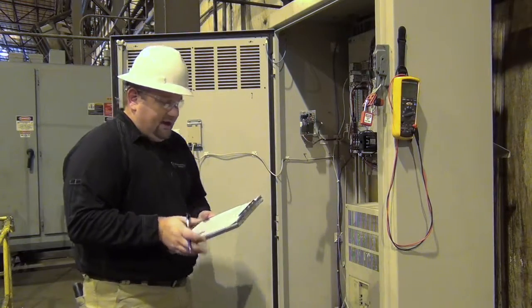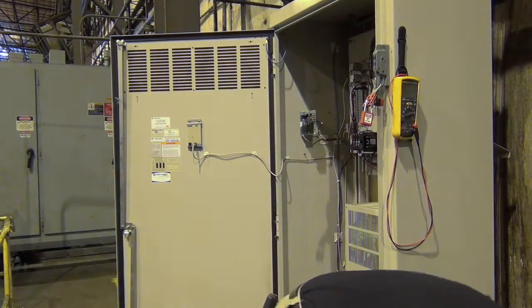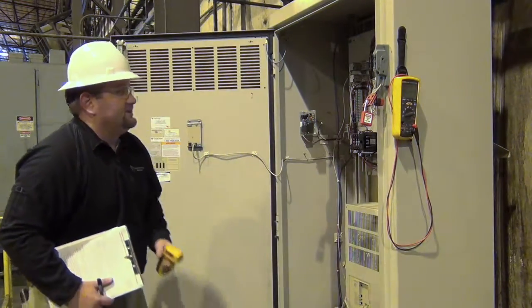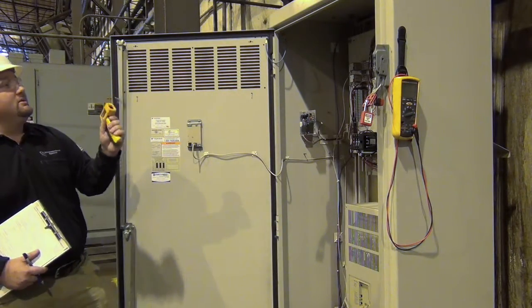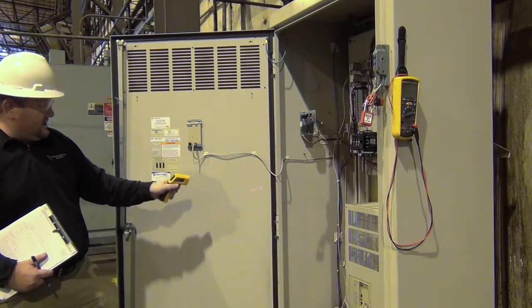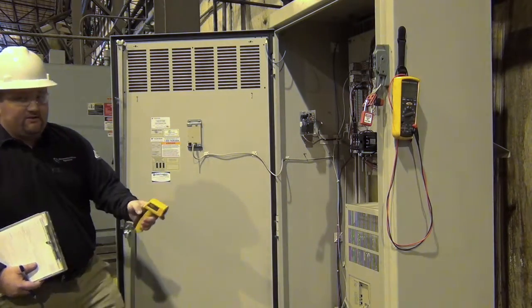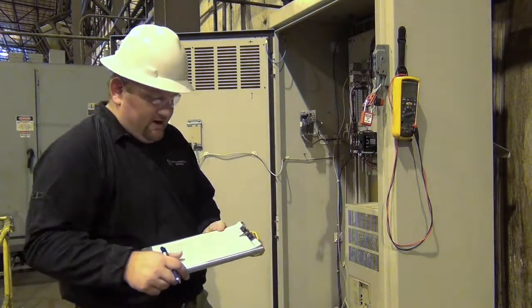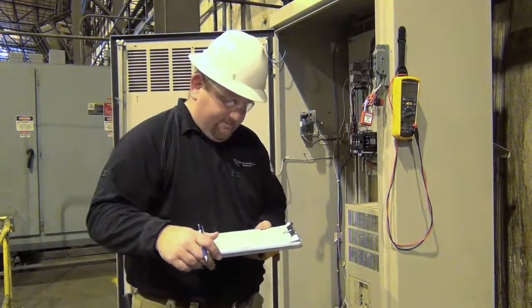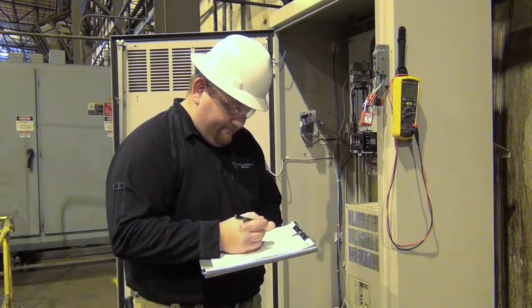What we do is take an ambient temperature reading. So what we're going to do is stand back and just shoot up and get an average here with our gun. So we're right about 75 degrees Fahrenheit in this building right now. Like I said, the line isn't currently running. We'll go ahead and make a note of that.